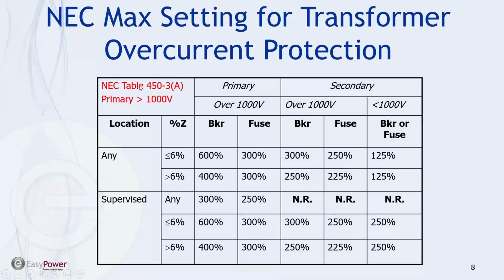So I referred to the NEC max table. This is in Table 450.3(A). And basically, for primary voltages under supervised or unsupervised conditions, the maximum setting, if we're using a breaker, is 600% under 6% impedance ratio or less. Greater than that would be 400% of the max current, full load current. And so this is a chart that we'll be referring to periodically as we go through this process.